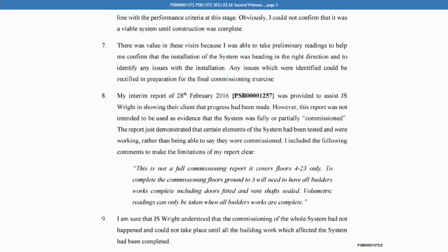And you say that you wrote in the report, this is not a full commissioning report. It covers floors 4 to 23 only. To complete the commissioning, floors ground to 3 will need to have all builders' work complete, including doors fitted and vent shafts sealed. Volumetric readings can only be taken when all builders' works are complete. So it would appear that the position was that when you attended in February, there were still works going on to the lower floors. Is that correct? Yes, that's correct. And that's why you couldn't commission the whole system? Yes, I understand.